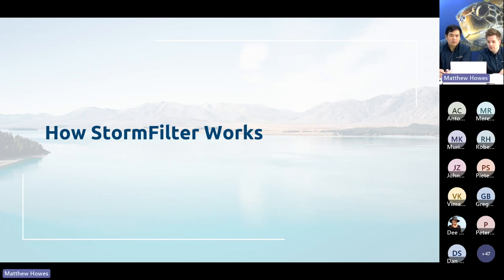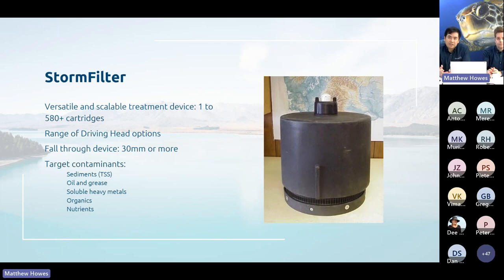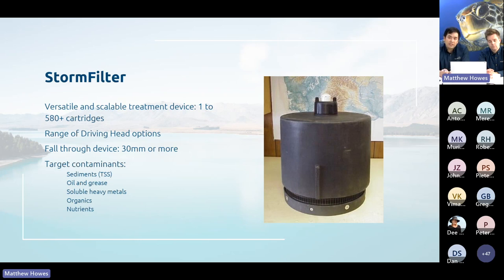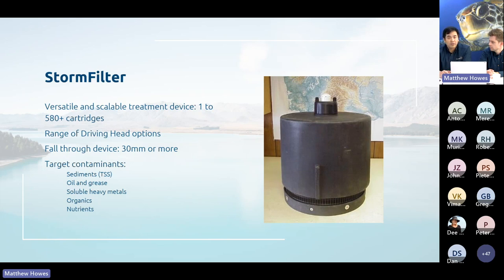Kevin explains: the Storm Filter is basically a siphon-activated cartridge system filled with media. It is versatile and scalable from a single cartridge in a car park or single house, all the way up to a 500-cartridge system treating 100 hectares of catchment. Cartridges come in a range of heights down to 350mm for sites with hydraulic restrictions, and the system can target different contaminants using different media — sediment, oil and grease, heavy metals whether particulate or dissolved, organics, and nutrients.